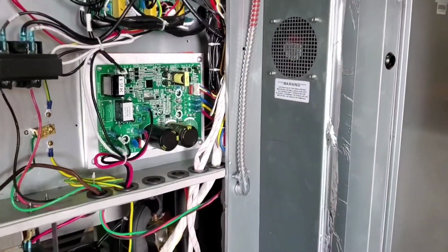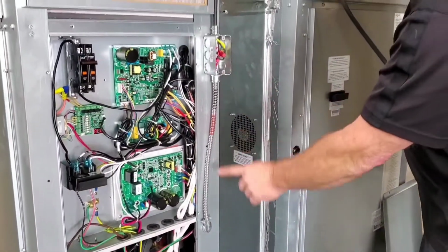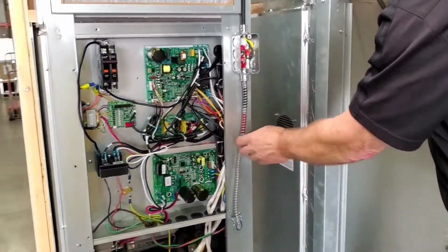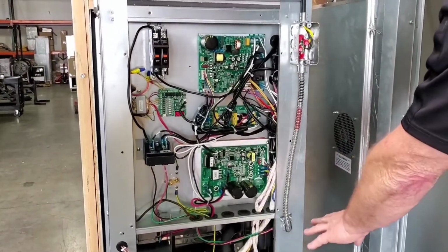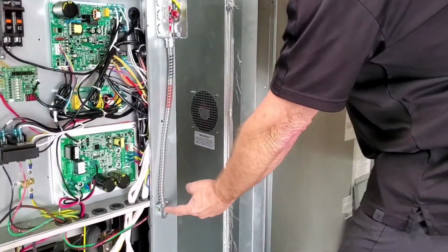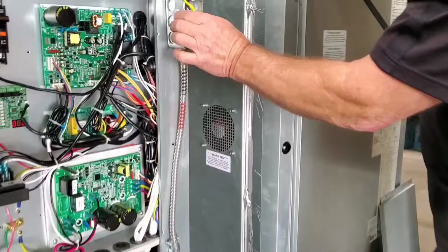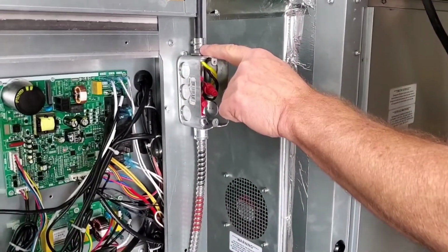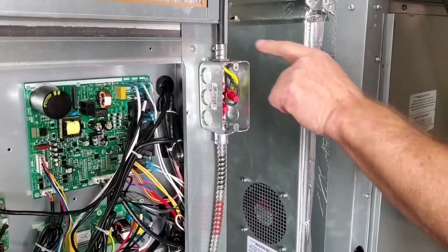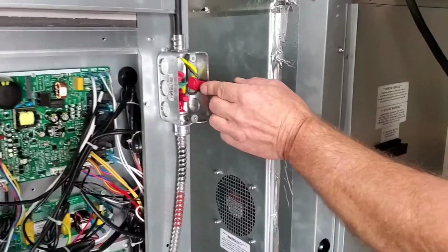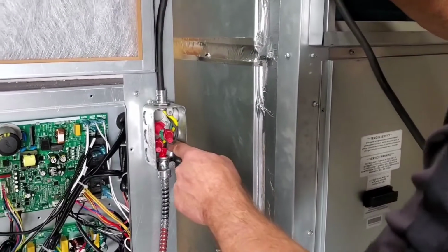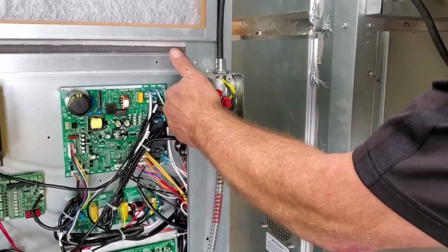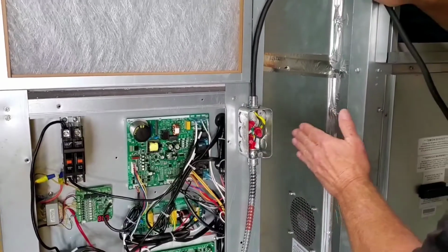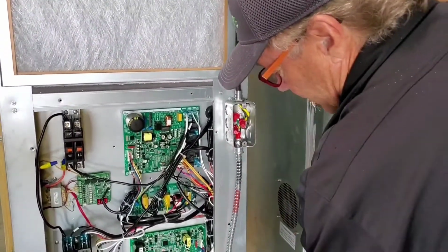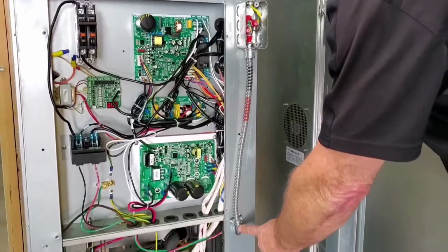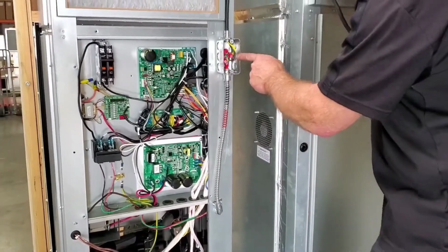So what you want to do is get a small J-box, about 4 foot of wire. Steel flex is the best to use because this is going to protect anyone coming up to the unit. It's up to code. You're going to want a 90-degree connector, a straight connector, a J-box, and you'll already have one connector with the First Company unit that this will be encased in. So you bring the wires through, connect up your 2 hots and your ground in the J-box, secure the J-box to the unit, and watch out for the screws back here. Make sure you keep it all the way over. And this is approximately 19 inches from the multi-manufacturing penetration hole to the First Company penetration hole.